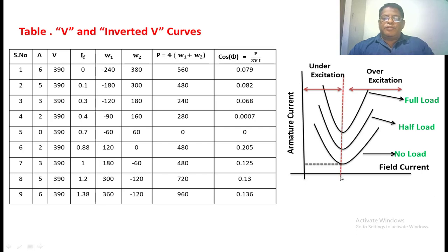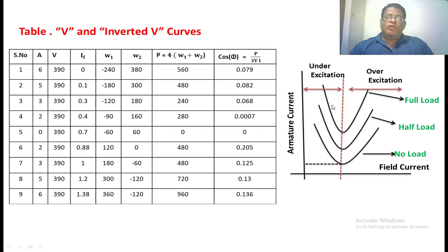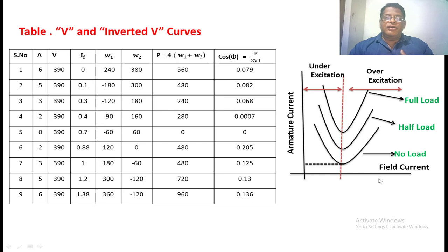The red dotted line represents unity power factor. Before this line is the under-excitation region, and above this line is the over-excitation region. In under-excitation mode, when we apply the field current below the dotted line, the motor operates at a lagging power factor — meaning the motor is absorbing reactive power. If we maintain the field current of the motor above this dotted line, the motor operates at a leading power factor and the synchronous motor is able to supply reactive power to the network.